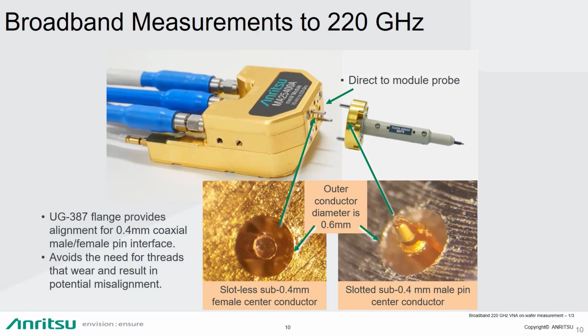So now we can see the interface between the module and the probe, and going back to our initial description of broadband systems and how we went from a 1.85 millimeter test port in the baseband VNA that can operate up to 70 gigahertz. We then went to a 1 millimeter test port connector in order to go up to the 110 and 125 gigahertz frequencies. We now need to go to an even higher frequency, and therefore we need an even smaller coaxial connector. We need to have a coaxial connector because we're, after all, trying to get down into the low RF frequencies, down to 70 kilohertz in this case.